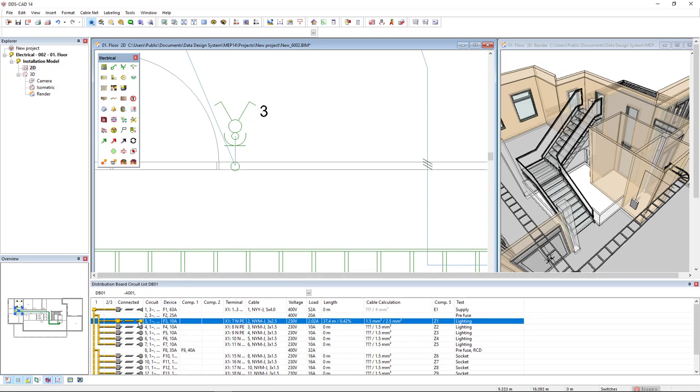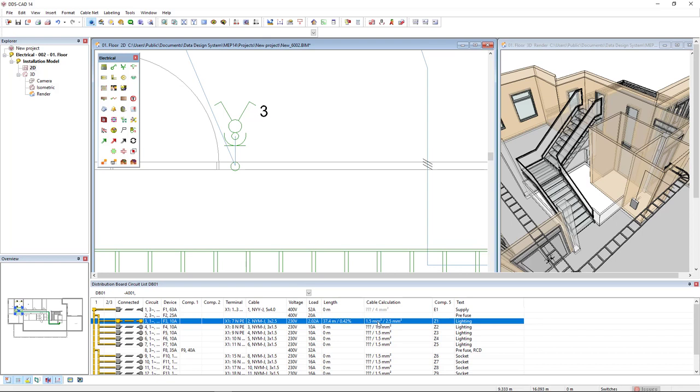In the connected column we see the circuit has been correctly connected from the board to the terminals. We also see in the load column the current load, in the length column the length of the cable from the board to the switch and the voltage drop. And in the column cable calculation we see on the right the cable we have selected and on the left what has been calculated. For the calculation 1.5 would be OK for this circuit.